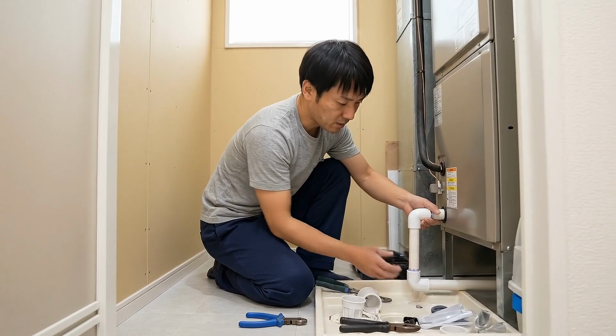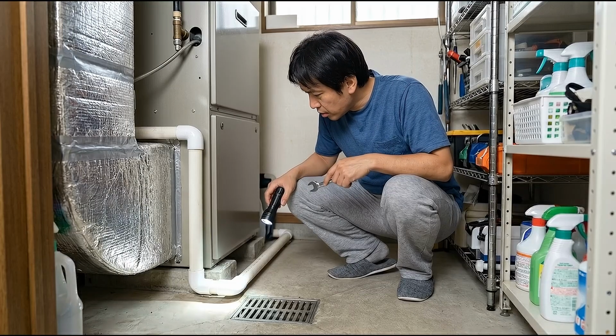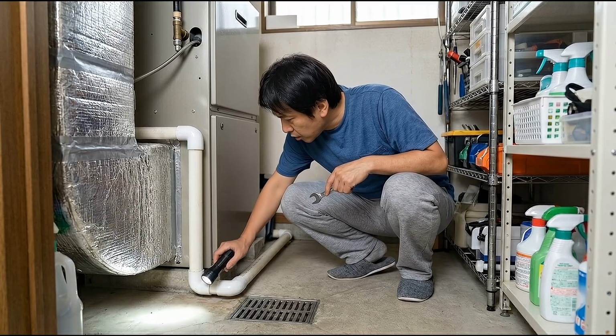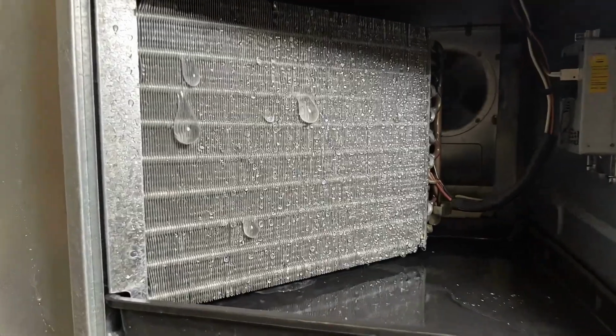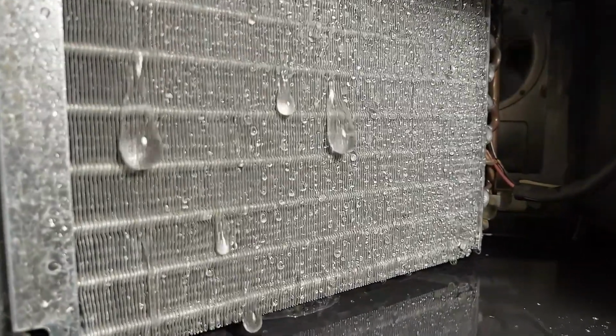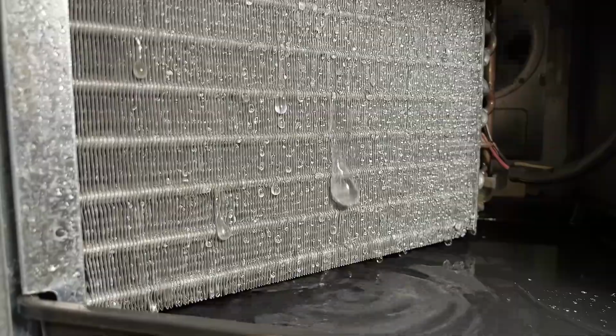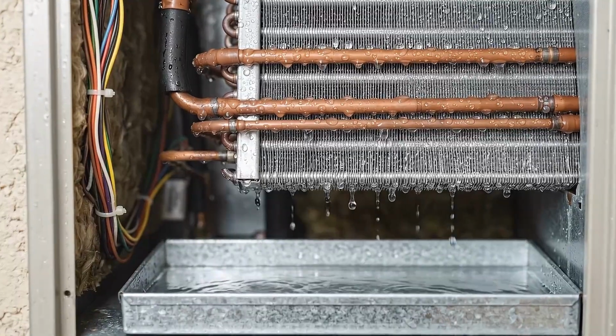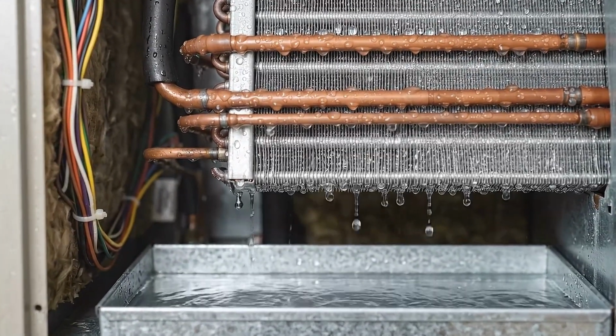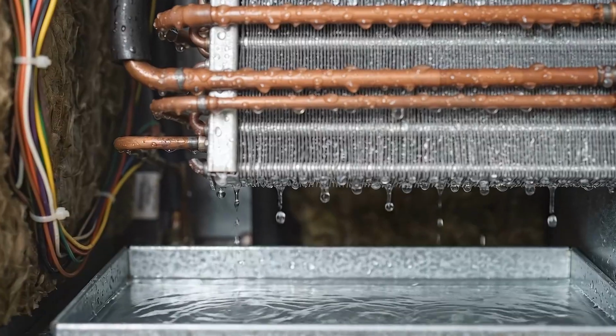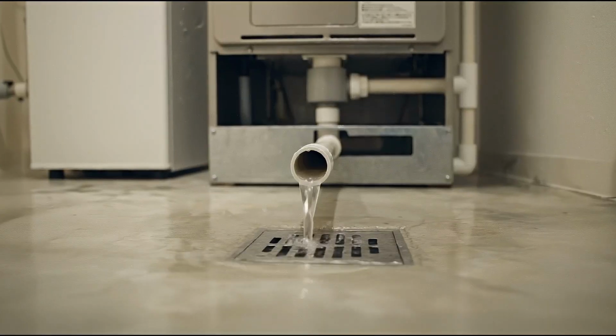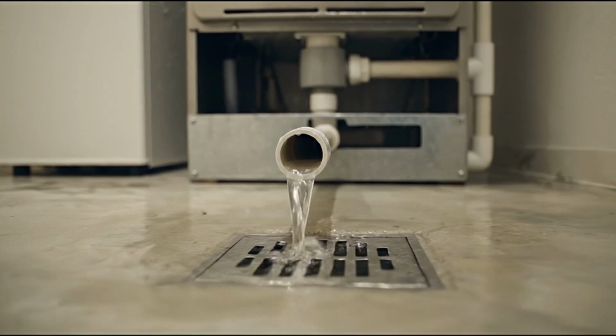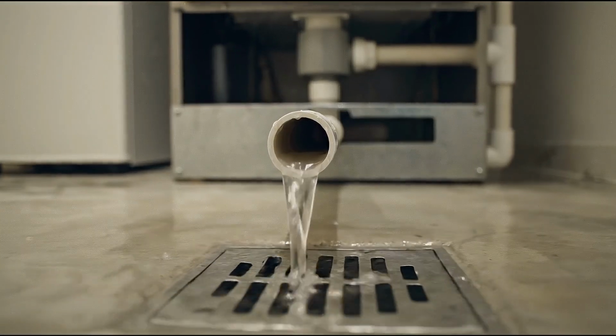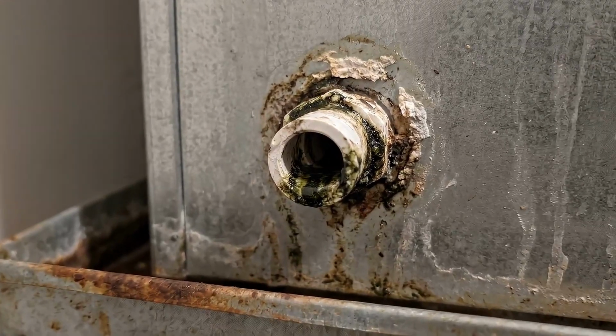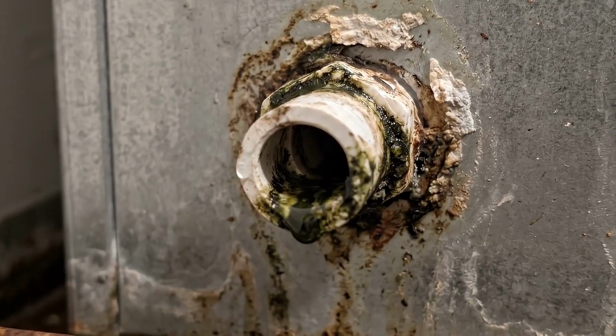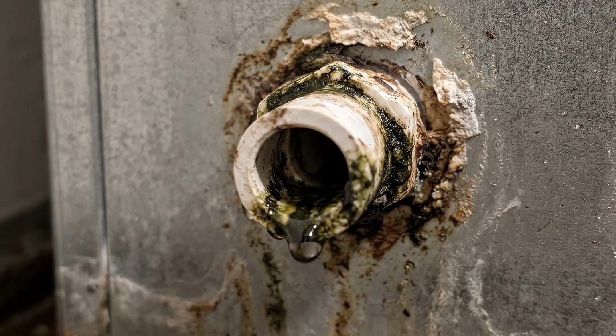One more part that gets overlooked, and this one causes problems that look unrelated to the AC itself. The condensate drain line. Every air conditioner produces water as a byproduct of cooling because moisture from the indoor air condenses on the evaporator coil and drips into a drain pan underneath it. From there, a small PVC pipe carries the water outside or into a floor drain. Over time, algae, mold, and mineral deposits can build up inside that drain line and block it.